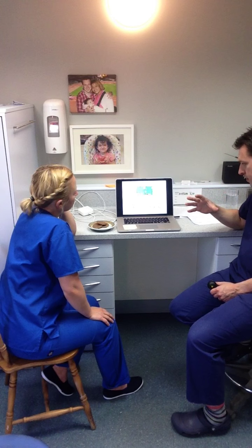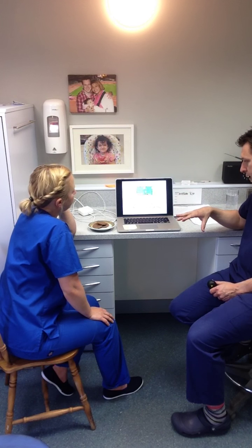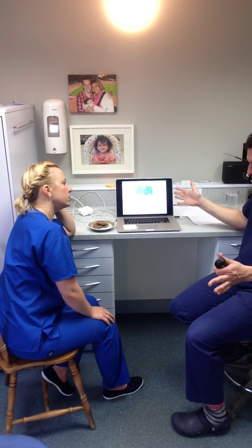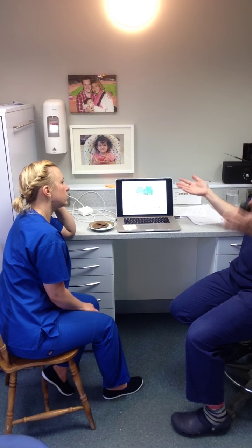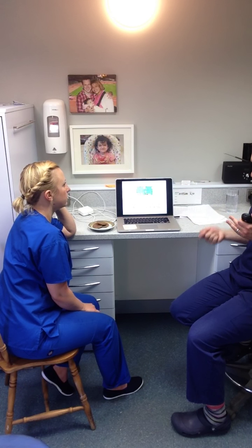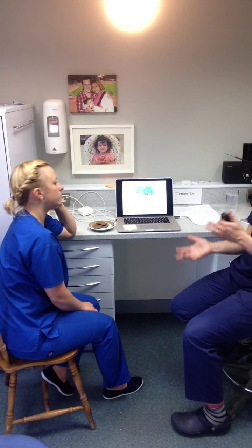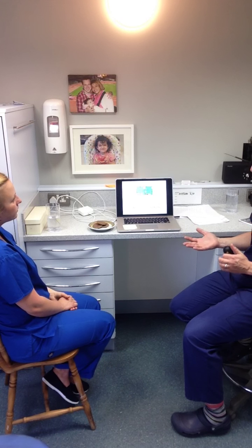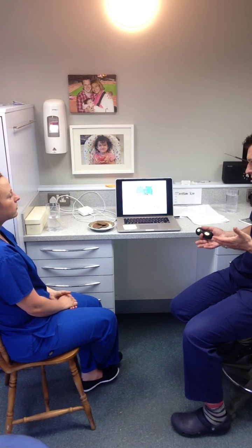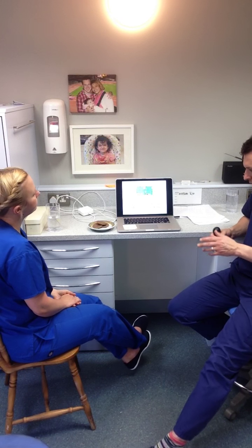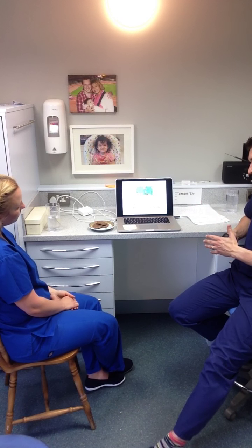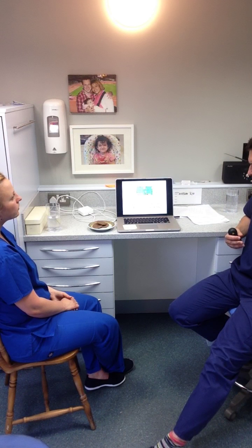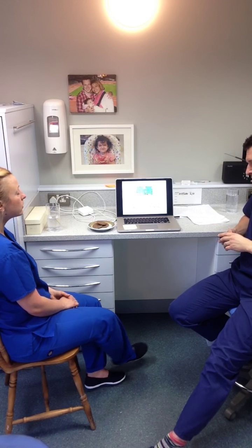So the dirty instruments come in. There's a washing sink, an ultrasonic cleaner, and then the washer disinfector. It's a double-ended washer disinfector that separates the clean side from the dirty side. On the dirty side you put the dirty instruments in, and there's another door on the clean side where you pull those out clean, and then it's completely aseptic. You don't need to worry about anything else. We have a logical process where the instruments come in through the decontamination room from the dirty side right through to the clean side. It's not best practice, but we comply with essential practice.